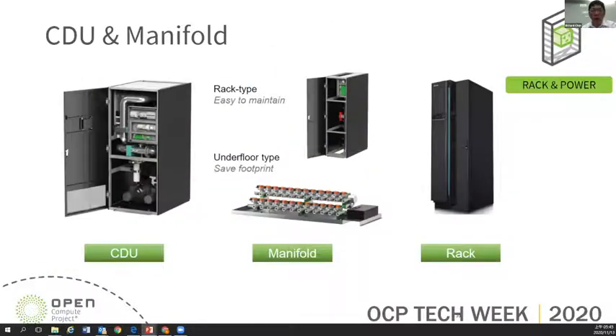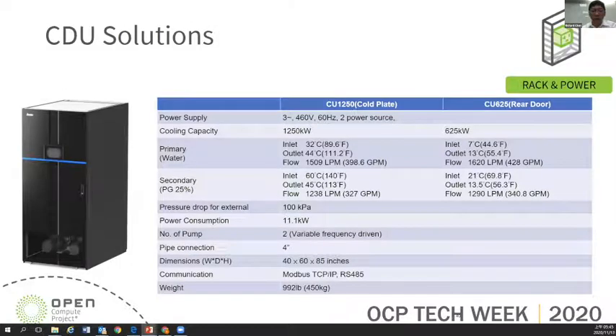For infrastructure level cooling, we have the CDU and the manifold to provide the cold water to the rack. The manifold includes the rack type and the underfloor type. The CDU capacity is 1.2 megawatt for cold plate cooling and 600 kilowatt for rear door heat exchanger cooling.